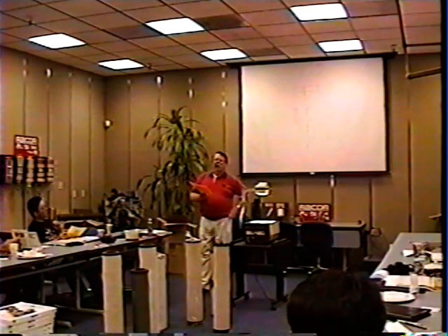So they're in the war room in their fuels building, and they heard this pop. And there was a vessel bigger than this one that we worked on. The lid ended up like 300 yards over here, and they had 1,200 gallons of fuel flowing. Actually, the dummy who turned the valve hadn't got too far away, and he got back and turned the valve off. But now, not only do you have the damage to the vessel, now you have an EPA spill that's going to cost you many thousands of dollars to clean up.